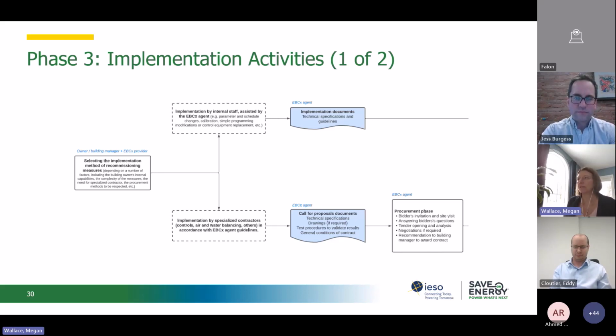So some of the measures will be able to be taken in-house, such as schedule changes, simple programming modifications, and maybe some calibration of sensors. Often in-house facility management can handle that. In that case, the EBCx agent would prepare the implementation documents to hand off to the in-house staff. Other methods will require an outside contractor, such as controls contractor, air balancing contractor, or other types of contractors. In that case, the EBCx agent would provide the technical specifications, any drawings required, and prepare the tender documents.